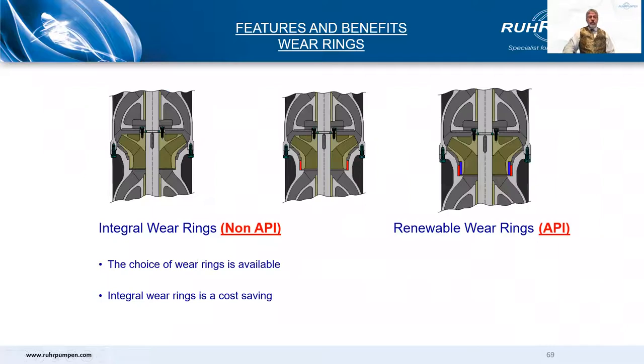The non-API pump may have integral wear rings — no replaceable wear rings — but the API pump will always have renewable wear rings, both case side and impeller side, as required by code. On the non-API version, we encourage you to start with integral wear rings. When the first major overhaul occurs, probably after about five years, you can machine and fit bowl wear rings at that time to renew the clearances. Then at the second major overhaul, say at about 10 to 15 years, you can machine and fit impeller wear rings. On the API version, you have them by code.